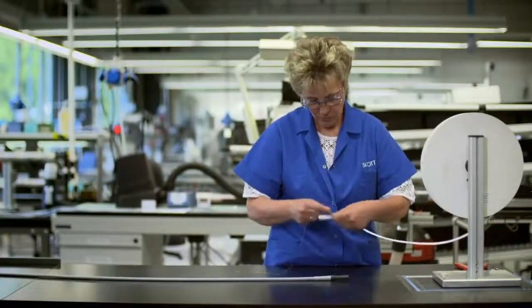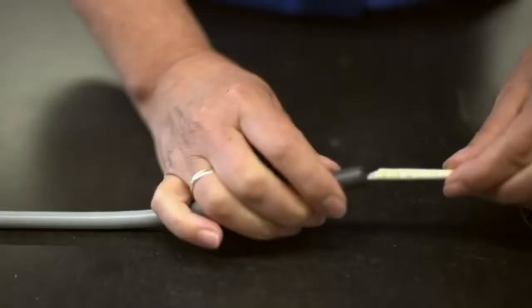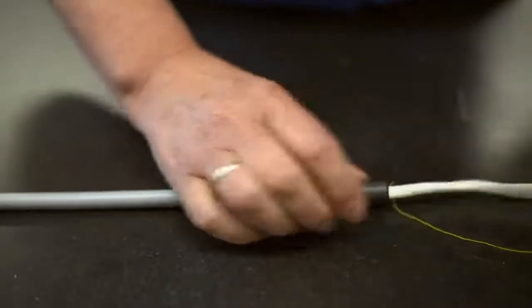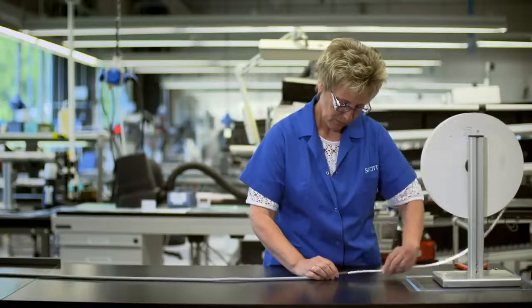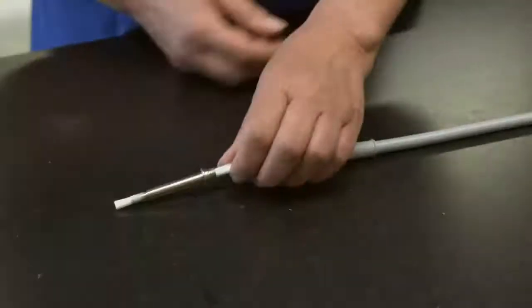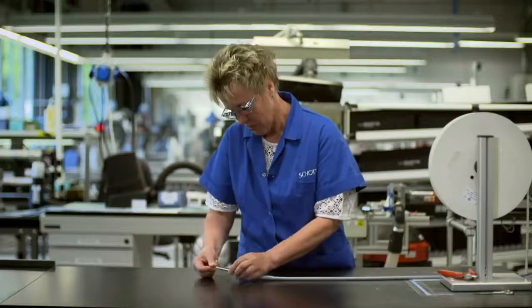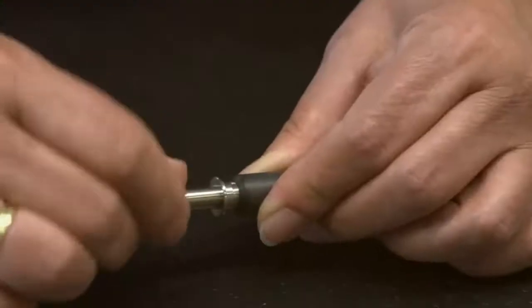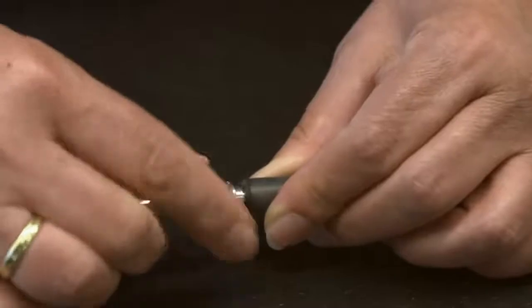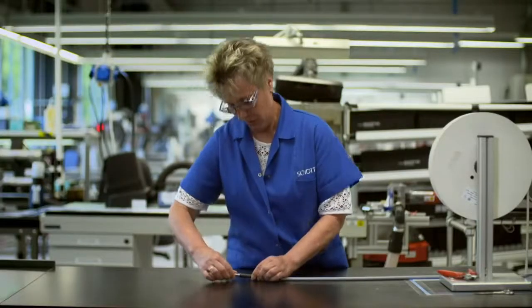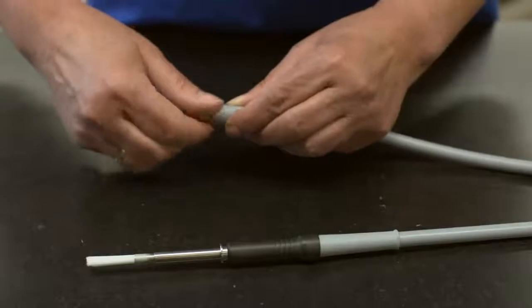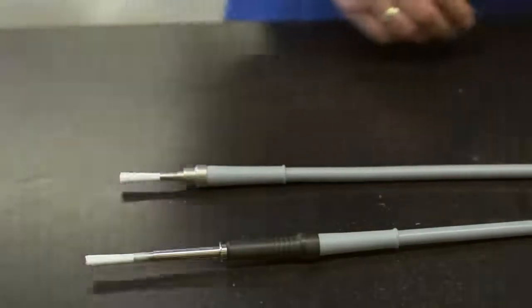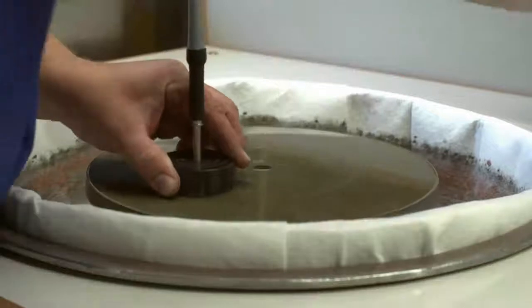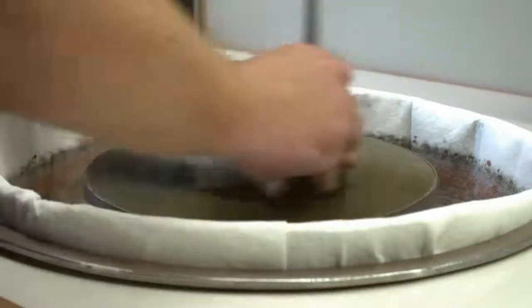To make the cable that will connect the operating room's light source to the endoscope, a bundle of fibers is inserted into a silicone cable sheath. This cable has 9,000 fibers. A stainless steel ferrule is then screwed onto each threaded end of the sheath. The inside of the ferrules and optical fibers are now coated with glue, before heat is applied to cure the adhesive. Any excess fibers are trimmed, before both ends of the cable are polished, which finalizes the dimensions and allows the light to shine through.